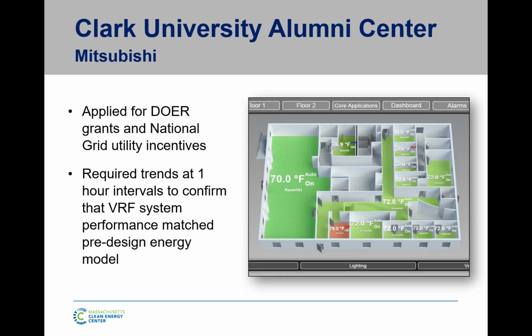They applied for a few different incentives and grants to build a building like this. And part of that required trends at 1 hour intervals to confirm that the system was performing as designed. And this pulled in watt hour meters. This pulled in a lot of different data points in the system so that they could go back and look at it for a year at 15-minute intervals and find out, did the system do what the pre-designed energy model said it would? And here's just an example: an advanced graphics package was added on top of it to show different, this is the actual floor plan.